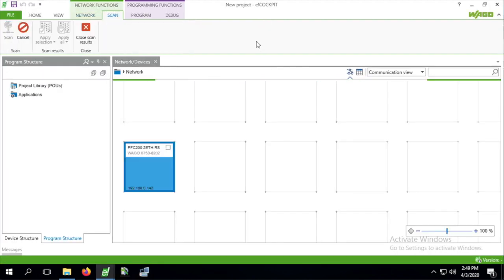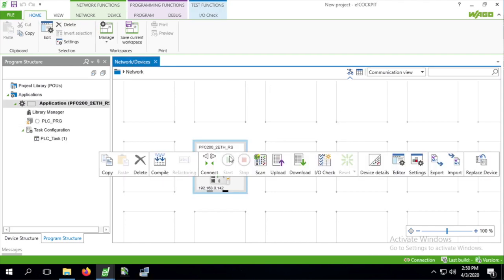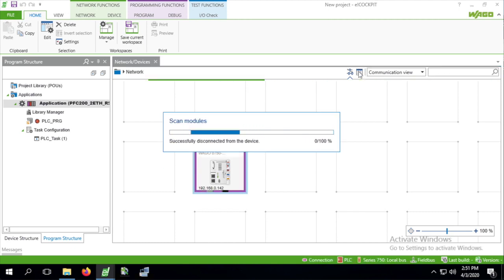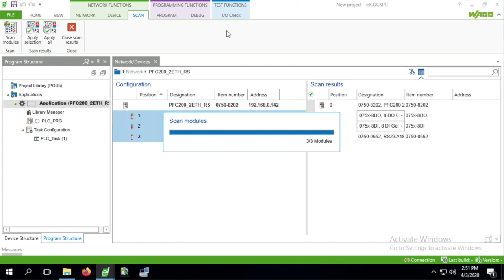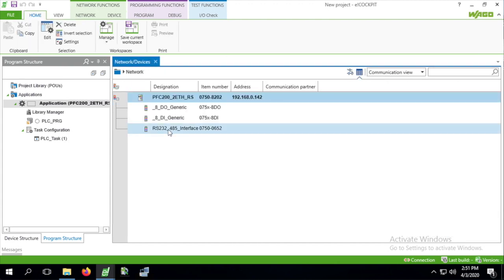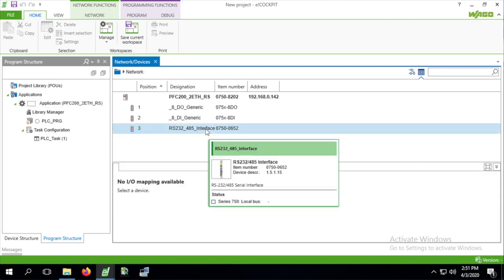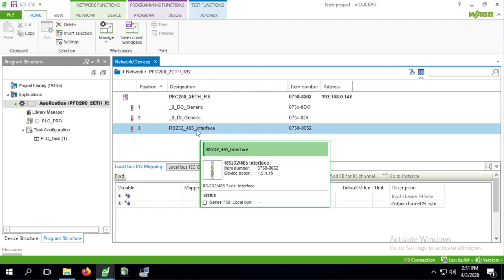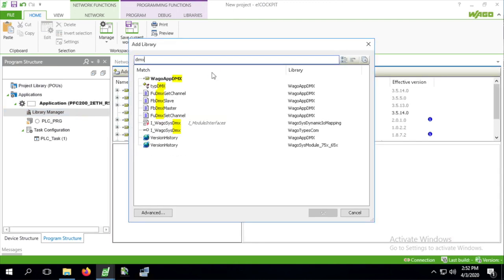Next we start a new project in e-Cockpit and do the normal setup for our 8202. Make a note of the 750652 module interface name as we're going to need that later. We also need the WAGO app DMX library which contains the master function block, so we add that to the project.